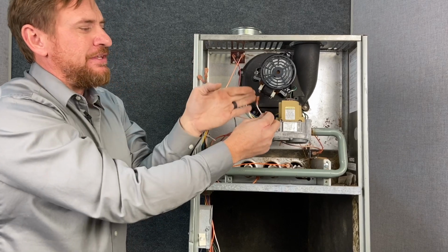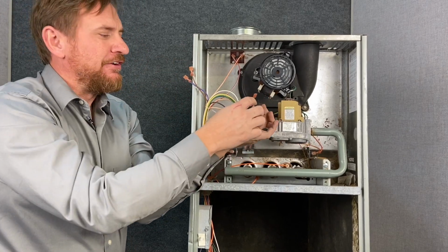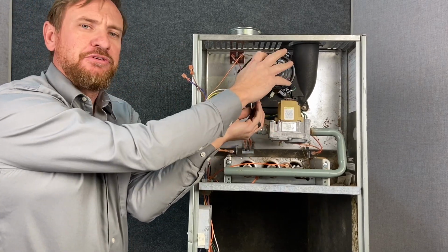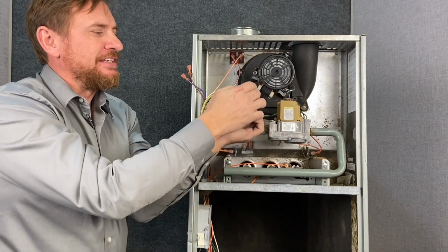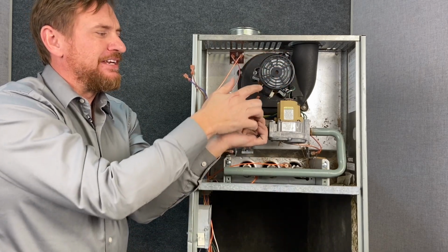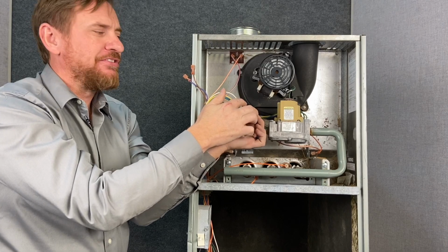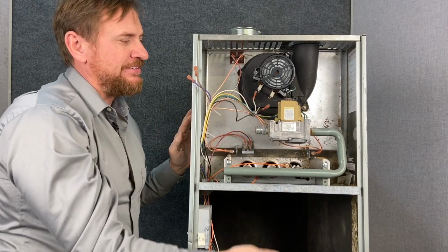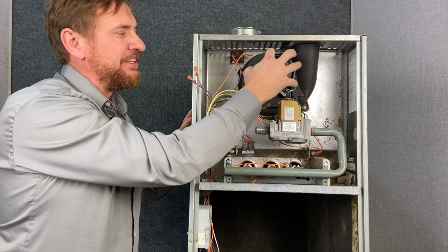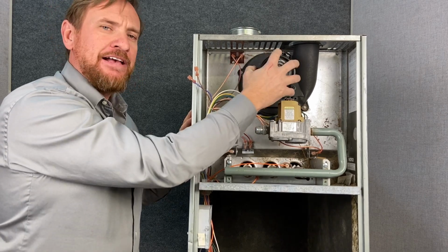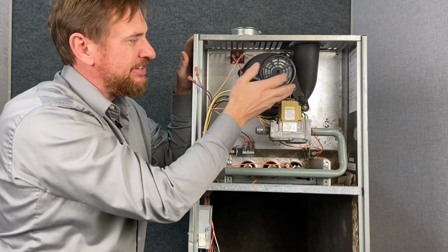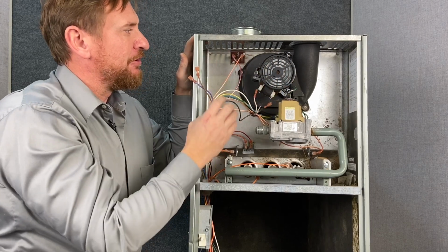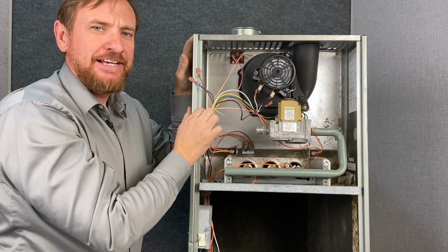But I'd want to make sure with this particular model, 115 volts. So if you saw this motor was not working, you had everything calling down there, you'd put your voltmeter here and here. You would check for 110 volts. If you were not getting that, you had a problem on this side. If you were getting 110 volts and the motor's not working, you look at the capacitor or the motor. And this particular motor does not have a capacitor on it. We're going to take this motor off so you can see what's happening on the back side of that.